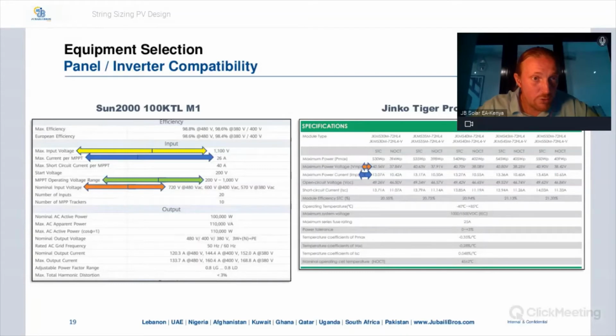So first, if you look at the orange arrow on the left and on the right, on the left, on the inverter, that is highlighting the nominal input voltage. Nominal input voltage means it is the voltage at which it will perform the best. So nominal voltage or rated voltage will tell you the optimum efficiency of that inverter at that voltage. So you can see there it says 720 volts at 480 volts AC. Okay. So again, what that's telling you is that the input voltage of the DC should be close to this number for the best production and performance.